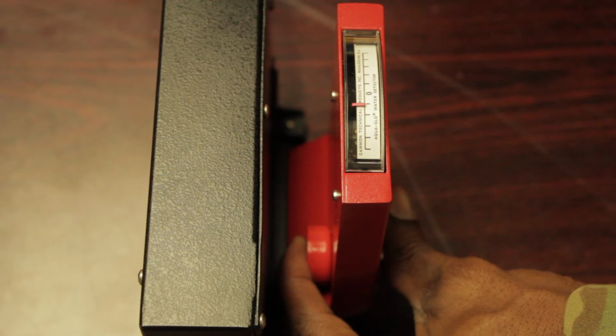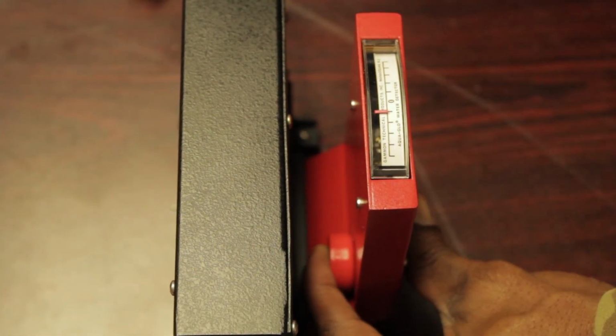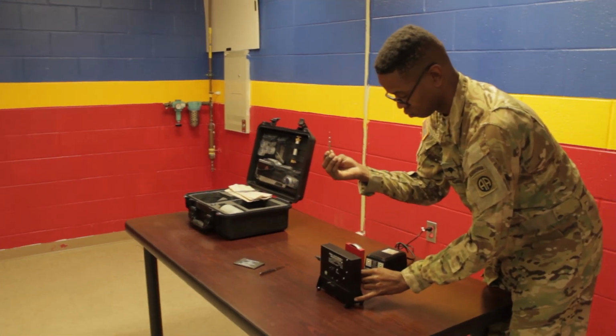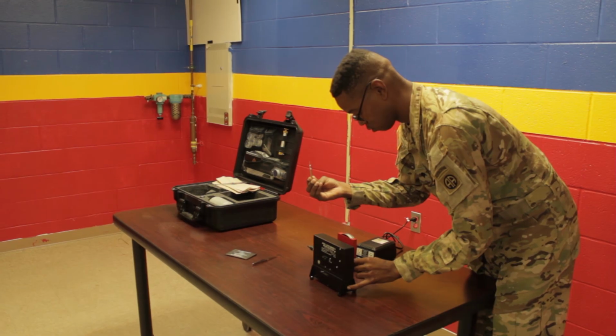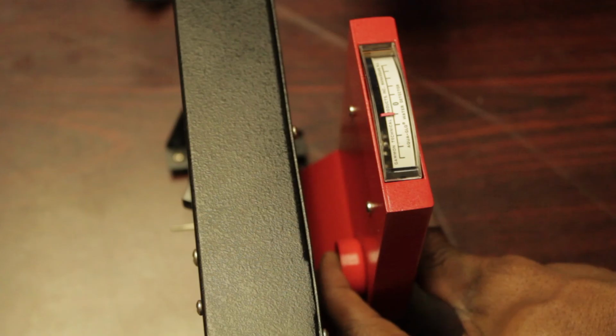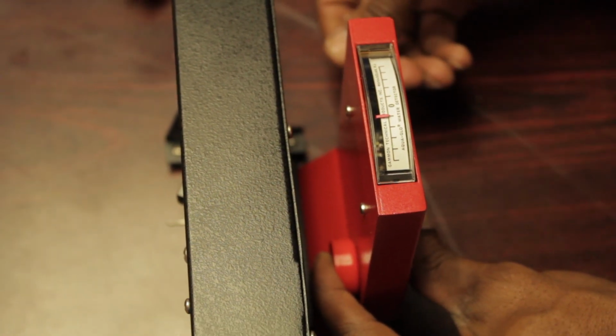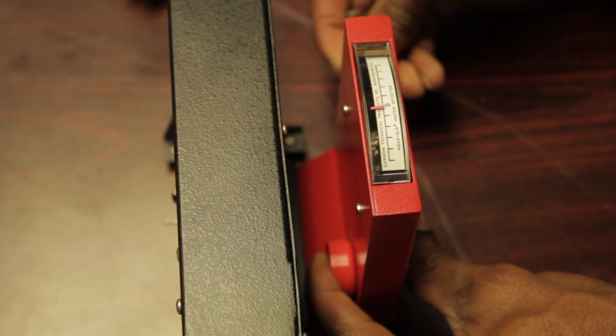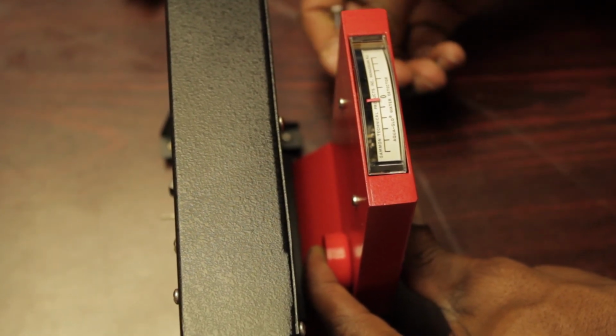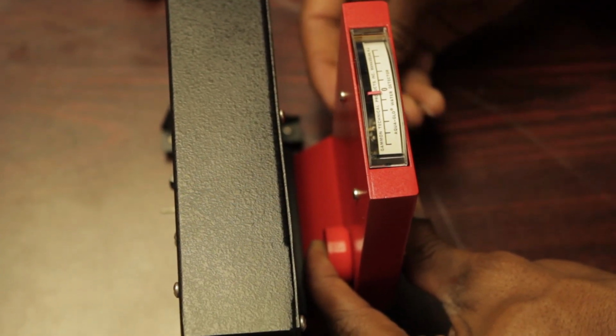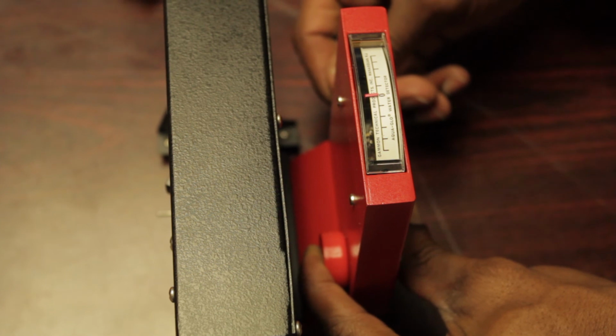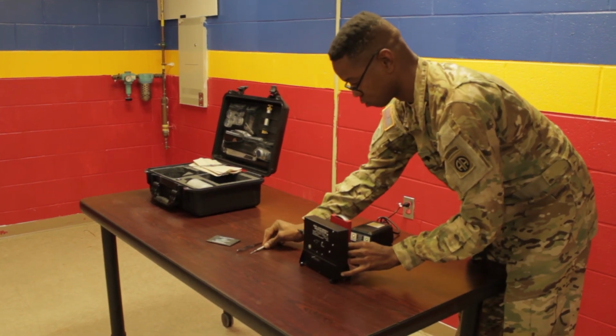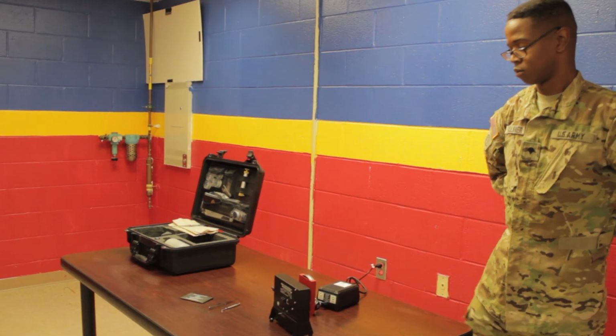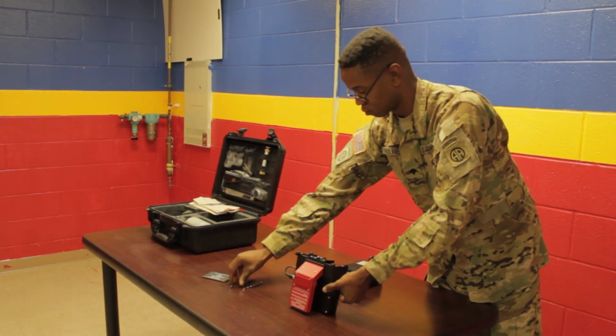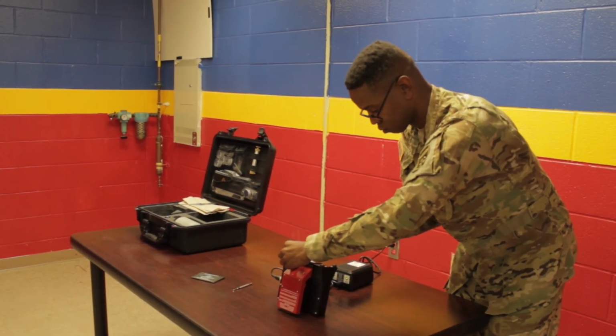If the meter reads any increment other than 0, you must insert a jeweler screwdriver into the small hole on the side of the meter assembly. While holding down the hooded button, turn the jeweler screwdriver until the meter reads 0, indicating that the meter is zeroed out. Using tweezers, remove the calibration pad from the test area and place it back into the protective sleeve.